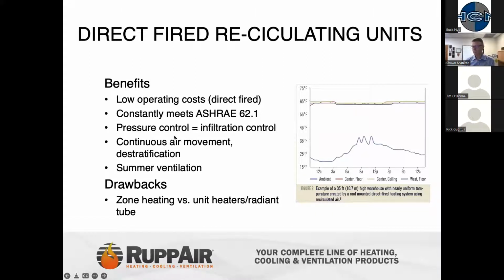If you're maintaining pressure in the space, you're going to mechanically control that infiltration. Continuous air movement helps eliminate destratification the best you can. Having those summer capabilities for ventilation we talked about. The biggest drawbacks to these units could be the zone heating versus the amount of unit heaters versus radiant tube heats. So in the case of a small building, you may get by with just one direct fire system, but you do lose some of the redundancy characteristics of that product.